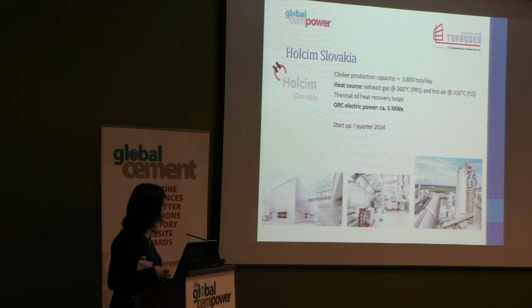In this case, there is also heat recovery from both sources, and the same thermal oil is the heat carrier for both sources, because the temperature of clinker cooler air was quite high, and so from an efficiency point of view, it was better to use thermal oil. And now it's been 1 year that this plant is operating. The ORC is inside this very nice building.